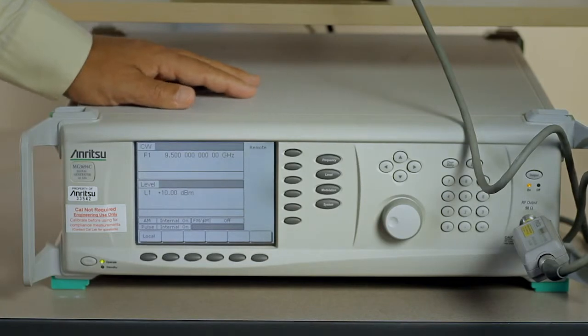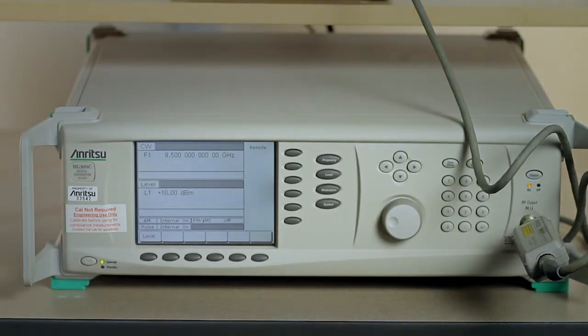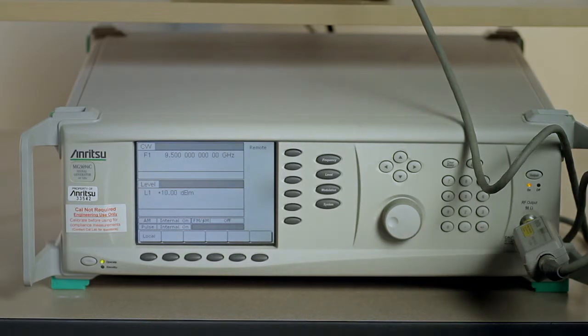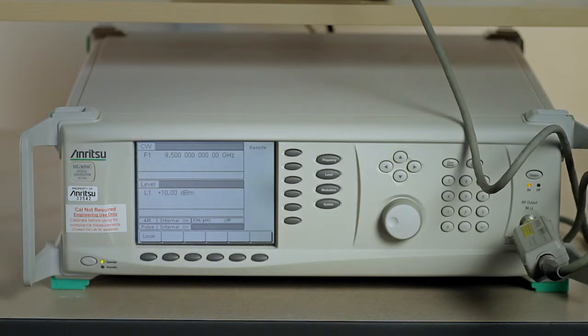Let's take a look at a fully functional LabVIEW application that's using Anritsu instrument drivers to automate radar return signal simulation and measurement. We are using an Anritsu MG3694C Low Phase Noise Fast Switching Microwave Signal Generator with its advanced pulse modulation capability to simulate a radar return signal.